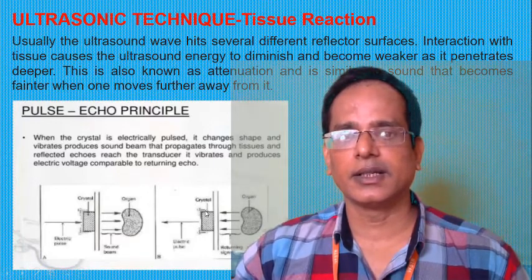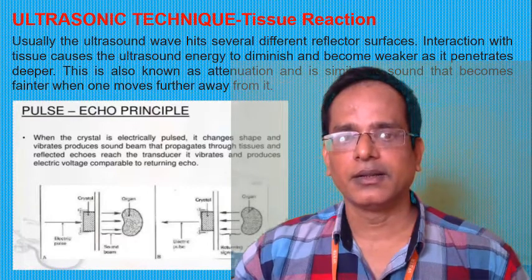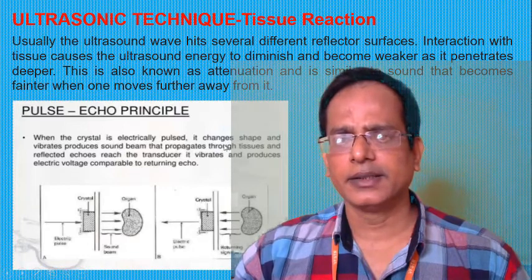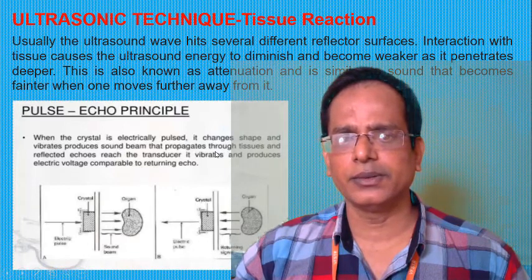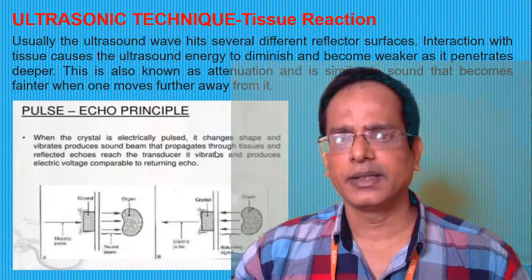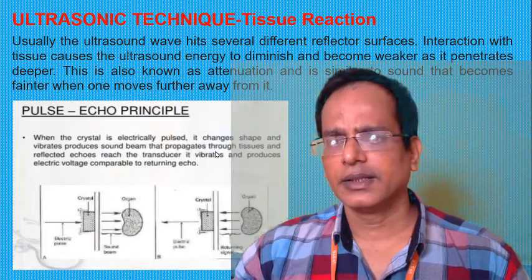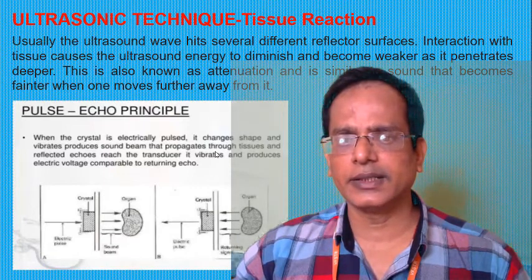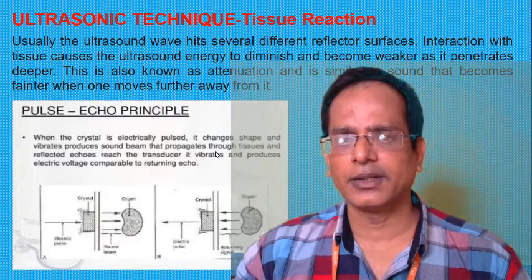This is the pulse echo principle. When the crystal is electrically pulsed, it changes shape and vibrates, producing a sound beam that propagates through the tissue. Reflected echoes reach the transducer, which vibrates and produces an electric voltage comparable to the returning echo.